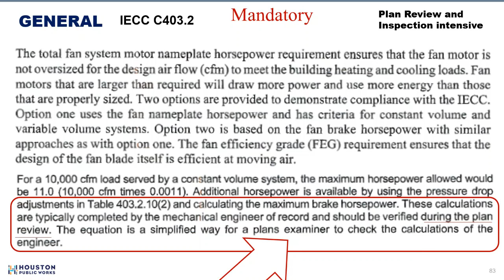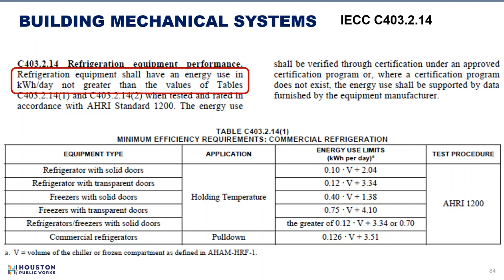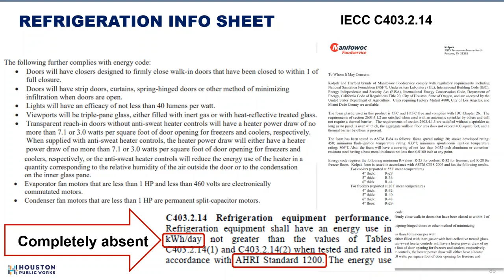All right, now let's look at refrigeration equipment. Refrigeration equipment shall have an energy use in kilowatt hours per day not greater than the values of this table here. Okay, so at the risk of getting in the weeds with that, here's a submittal that was with a fast food restaurant. Manitowoc is the manufacturer, and they had I think a 3-page or 4-page submittal, which was put into project docs. Completely absent from this sheet was anything about kilowatt hours per day. Completely absent. So that is a fail. I can't believe that a manufacturer would actually do that. Go to the plans, and there's something in the mechanical drawings about refrigeration, but this is more about refrigerant and a Freon leak detection system, and not a word about the refrigeration equipment kilowatt hours per day. Completely absent.